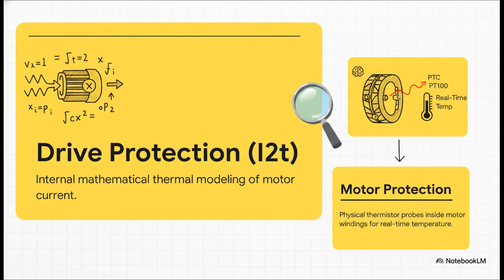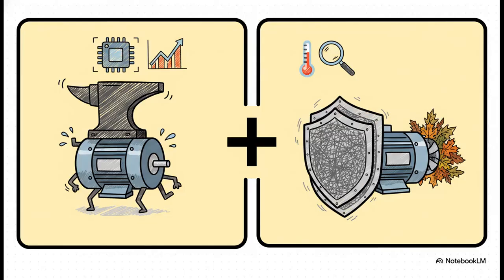On the flip side, motor protection uses physical PTC or PT100 thermistor probes. These are embedded directly inside the motor windings to give us a real-time physical temperature reading. Now, here's a massive pro tip on how the ATV320 handles this. You don't have to choose. It allows you to combine both methods at the exact same time. And this is a real game changer, because using the internal math doesn't disable the external probe monitoring. By running both, you're giving your equipment two independent layers of armor. The math catches overloaded operating conditions, while the physical probe catches environmental issues, like say a blocked cooling vent, that the math might completely miss.